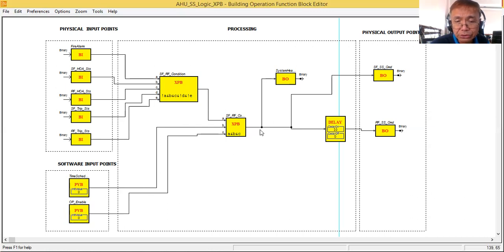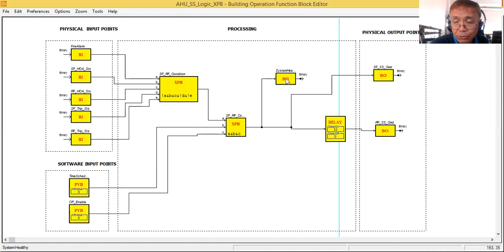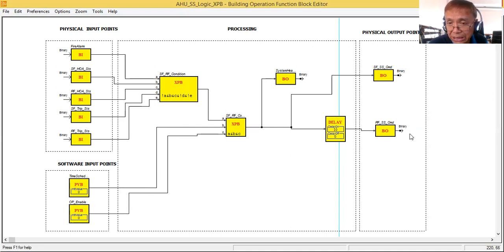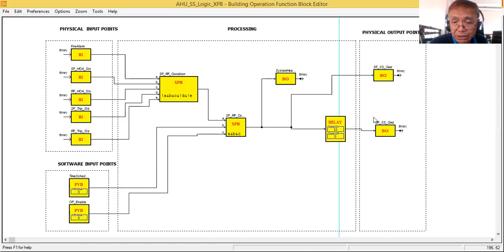If the first expression block output is true, the time schedule is true, and operator enable is true, the output will be one. When the output is one, a time delay starts counting the specified on-delay. After that delay, the return fan command becomes one, and the supply fan startup command is already true.